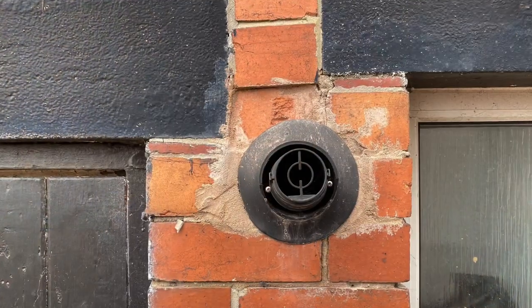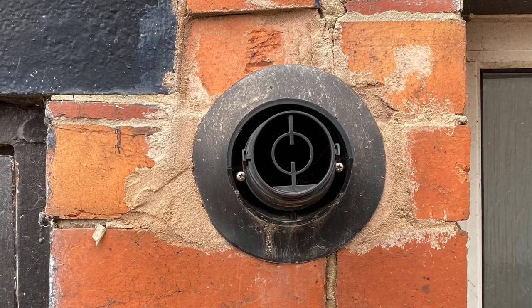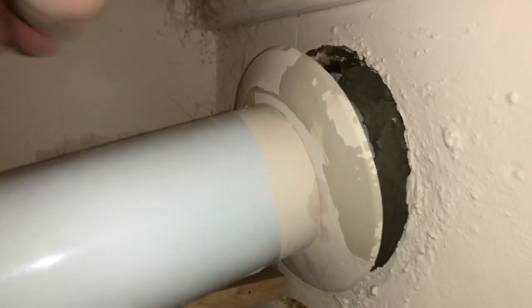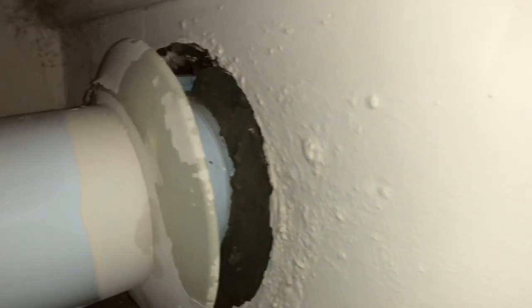This is showing a flue straight through the middle of a supporting wall that's supporting two lintels. This shows another flue joint that's in the wall — if the flue came off you wouldn't know, and you'd have to check the installation instructions for that.